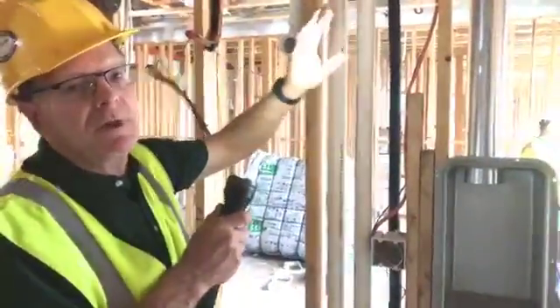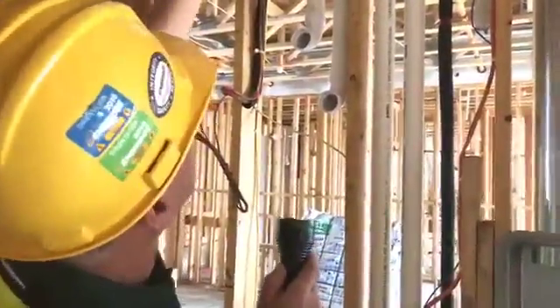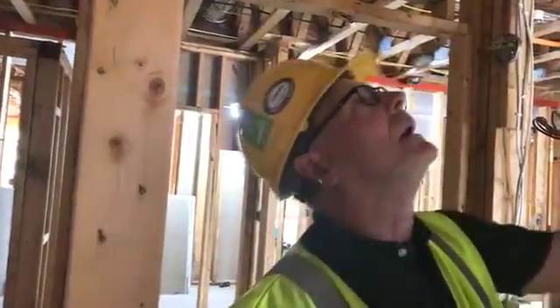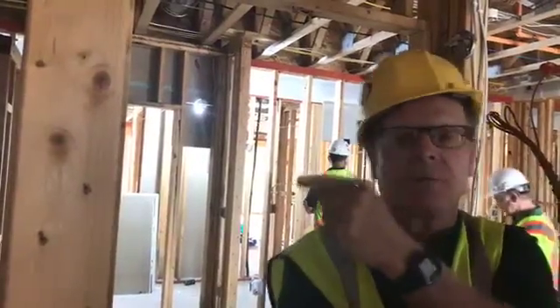Okay. This unit's going to be a little different to test for a duct system. Because of the glass area for the ventilation requirement, there's this fresh air makeup duct. It is insulated to reduce any potential condensation, interstitial condensation between the floors, right? Well, it is timed so that when the air handler comes on, we draw air, but it's also timed to our bathroom fan. This is a one bathroom unit. A bathroom fan has to have a certain CFM for LEED, for Energy Star. And it's going to be a little interesting to try and test a system that is drawing air in, trying to do a blower door. How does this work? Or when we're doing our ventilation testing for the bathroom fan, how does that work?